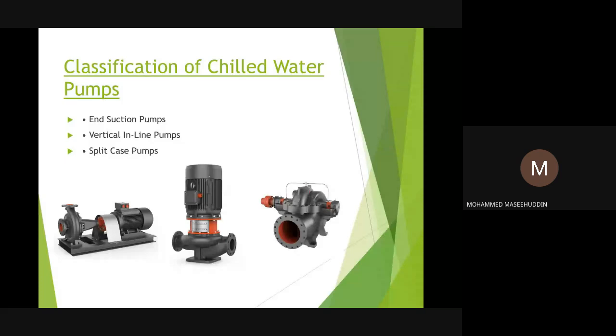So the system pressure, mostly in the chill water segment, will not exceed about say 12 bar or 13 bar, maximum 15 bar, based on the type and size of the building itself. So these are the three different kinds of pumps with different orientations. The first one is horizontal. The second one is vertical. The third one is horizontal as well, but it gives larger flows and large heads, and it can sustain a lot of pressure as well, up to 30 bar. So these are three kinds of pumps which are normally used in chill water applications.